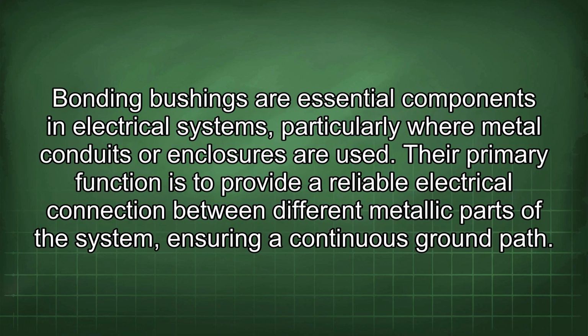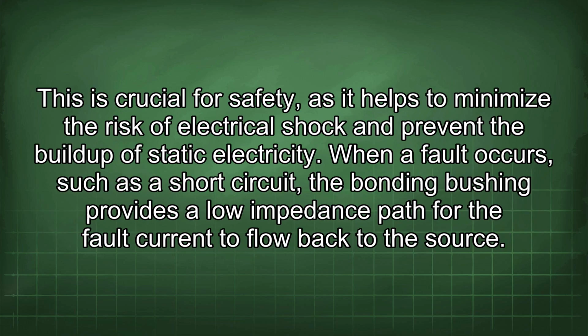Bonding bushings are essential components in electrical systems, particularly where metal conduits or enclosures are used. Their primary function is to provide a reliable electrical connection between different metallic parts of the system, ensuring a continuous ground path. This is crucial for safety, as it helps to minimize the risk of electrical shock and prevent the buildup of static electricity. When a fault occurs, such as a short circuit, the bonding bushing provides a low impedance path for the fault current to flow back to the source.